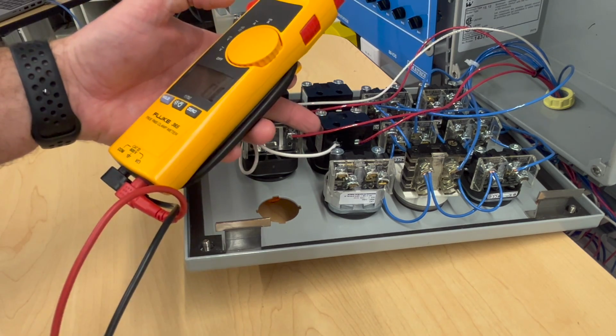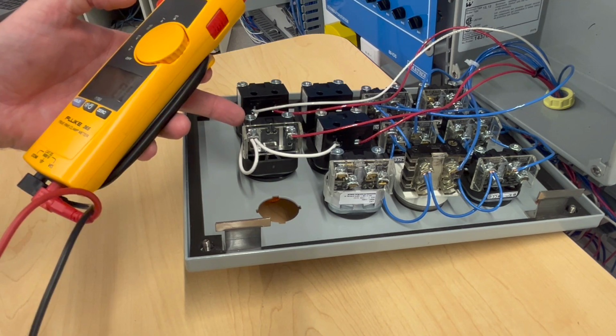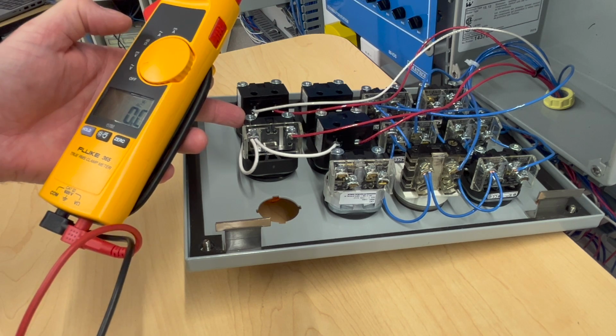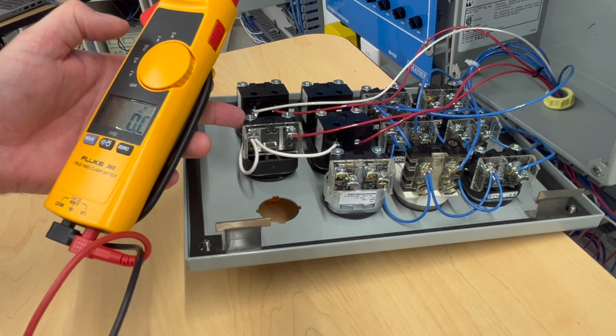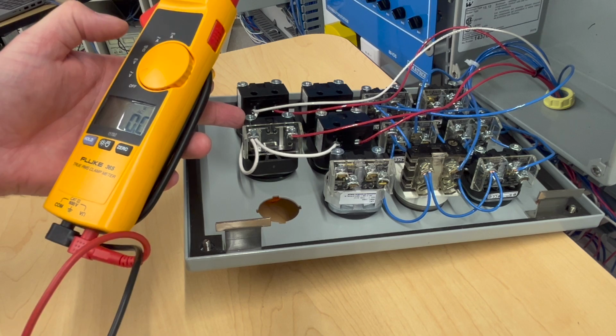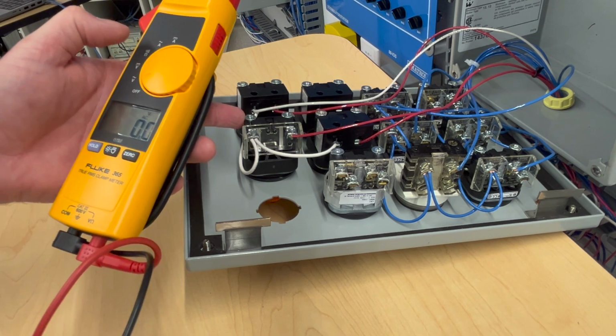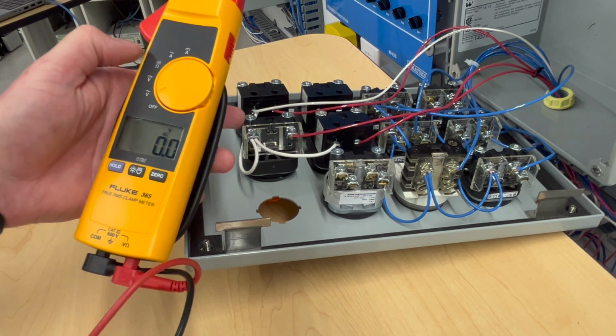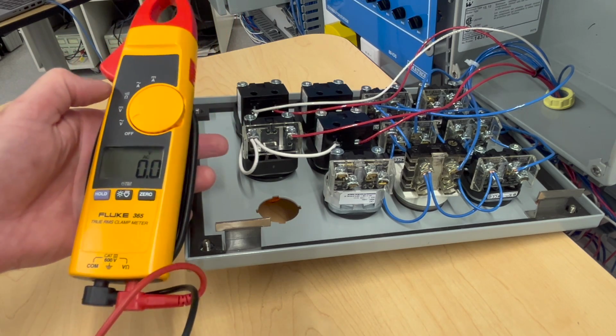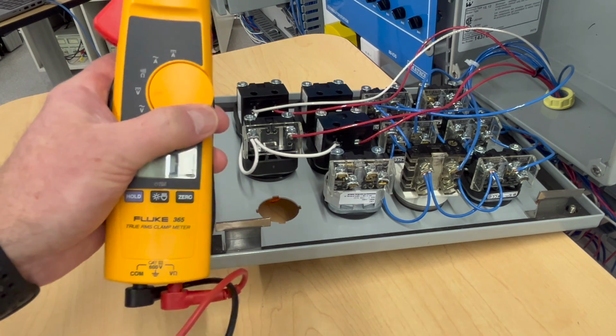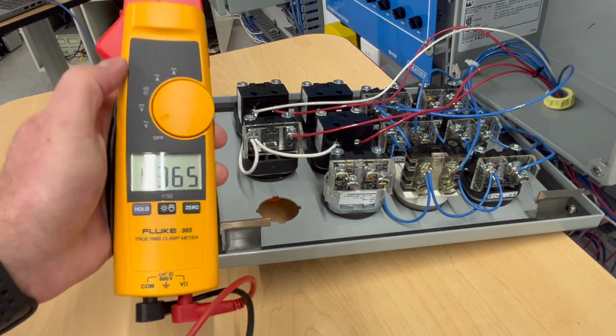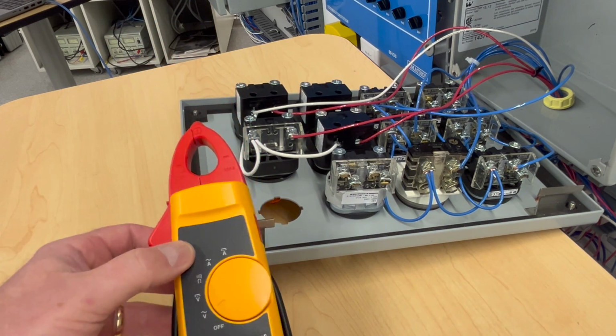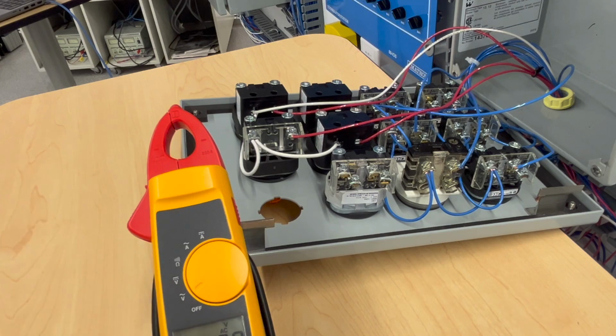The red wire here coming to the output indicates that this is AC, and most of the time the color code can be trusted. But you always want to be careful. You may want to go look back at the schematic just to verify, or if you're really unsure, you might want to take the voltage measurement as both a DC setting and an AC setting. Now I'm confident that this is an AC circuit.